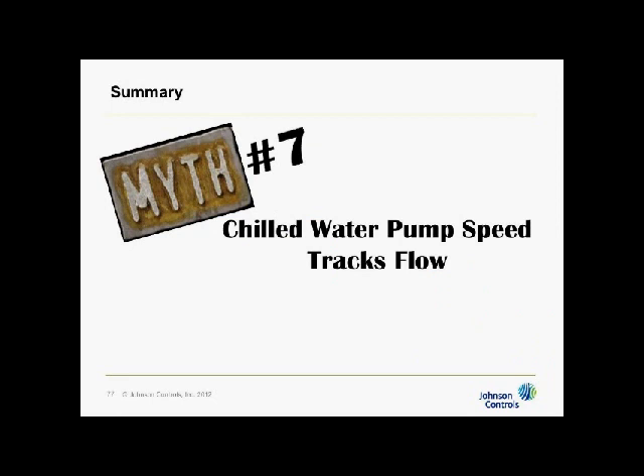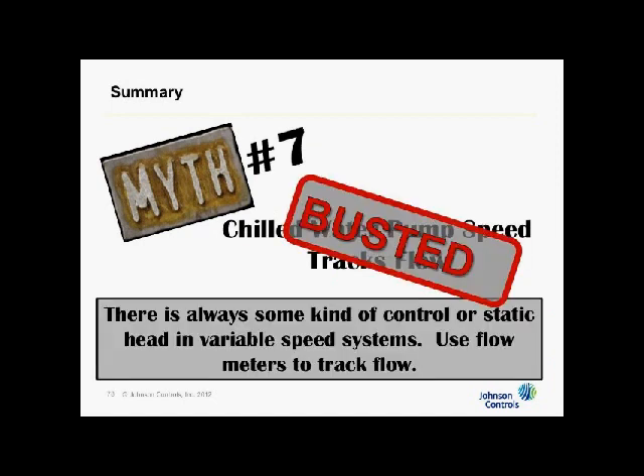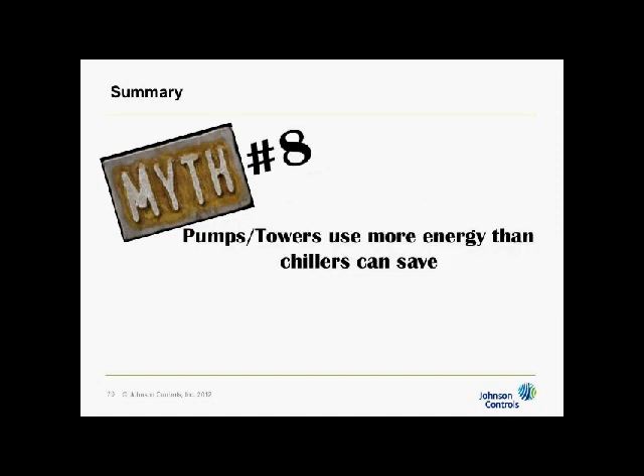Myth number 7, we talked about, said chill water pump speed tracks flow. That is busted. There is always some kind of control, static head, or other considerations in variable speed systems. You really need to use flow meters to track flow, but more importantly, to get the most efficient plant operation.